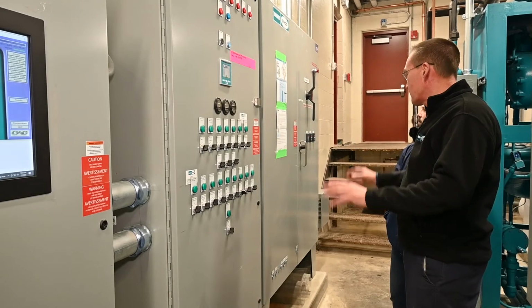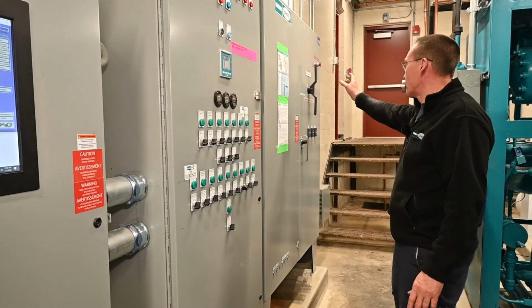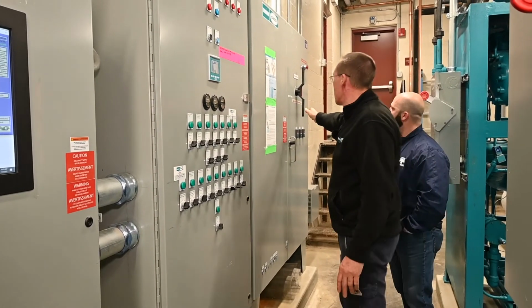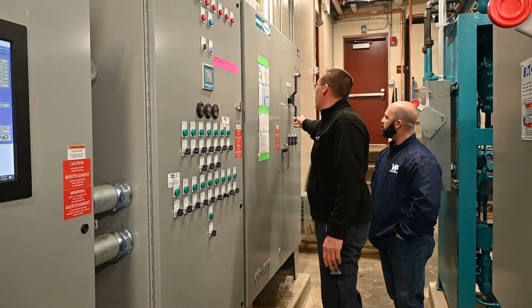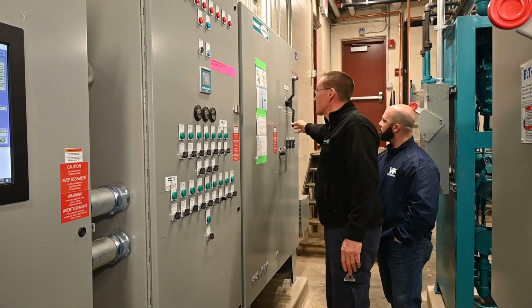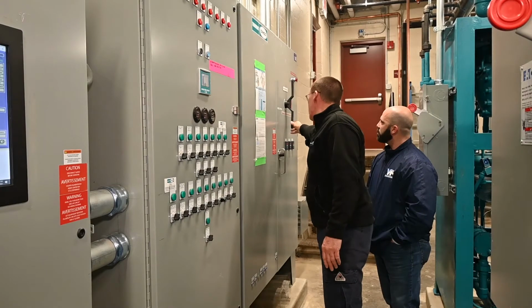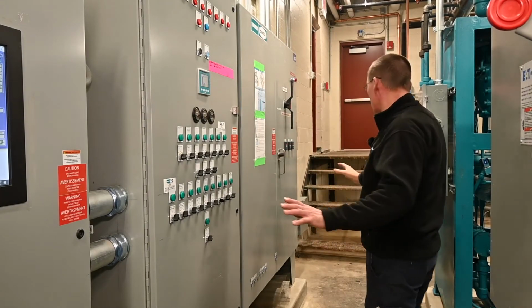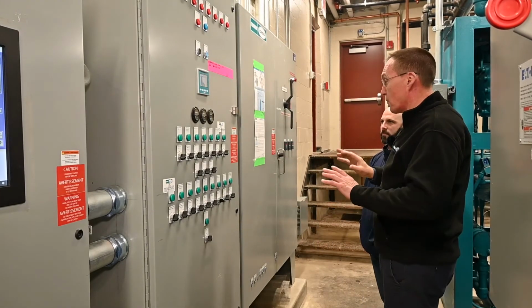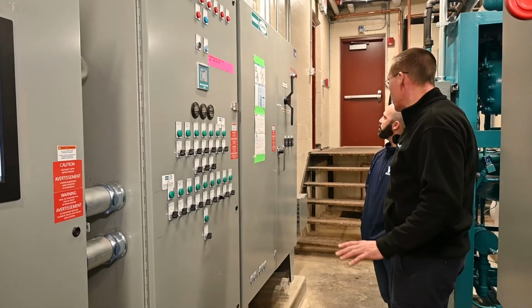So this is your main panel. On this side of the panel, we have your main disconnect switch. This is a T-handle that, if you needed to shut it off, is spun clockwise to the horizontal position. That kills all power to this package. All 480 will be dead. Everything will be shut down.